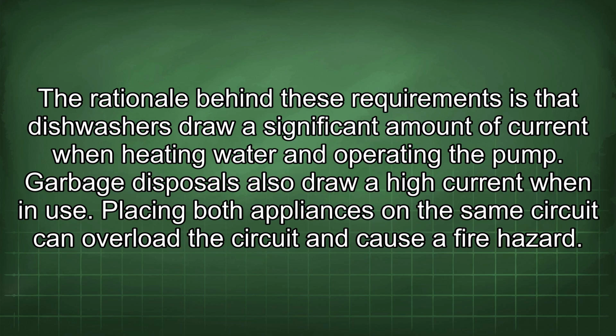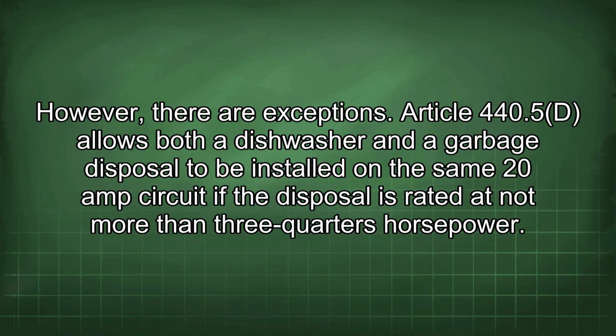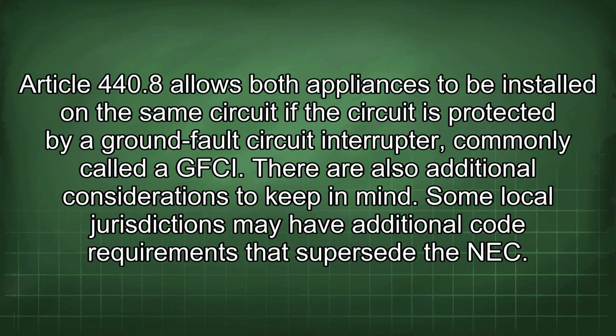pump. Garbage disposals also draw a high current when in use. Placing both appliances on the same circuit can overload the circuit and cause a fire hazard. However, there are exceptions. Article 440.5d allows both a dishwasher and a garbage disposal to be installed on the same 20-amp circuit if the disposal is rated at not more than 3/4 horsepower. Article 440.8 allows both appliances to be installed on the same circuit if the circuit is protected by a ground fault circuit interrupter, commonly called a GFCI.